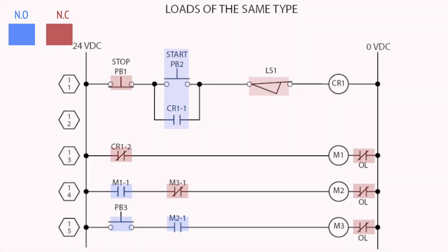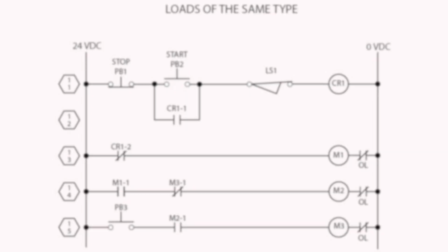All switches and contacts are classified as normally open, NO, or normally closed, NC. The state that we see on the electrical control diagrams is the state that the device would be found in when it's bought and not installed in a circuit. This is referred to as off-the-shelf or de-energized state. It is very important to learn this concept, as this is the state in which the switches are drawn in a circuit. When we mention de-energized position, we are referring to the component position when the circuit is de-energized, or when there is no power in the circuit.